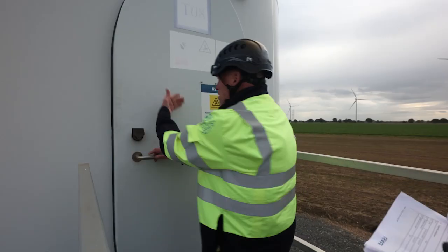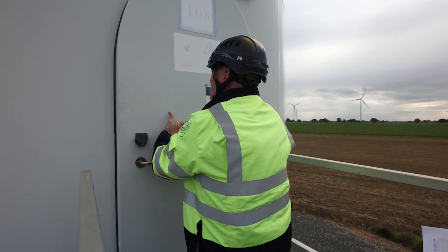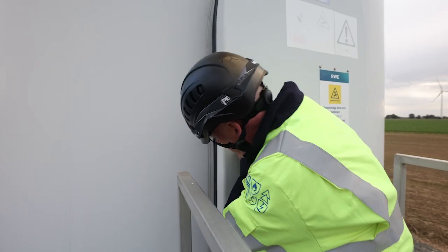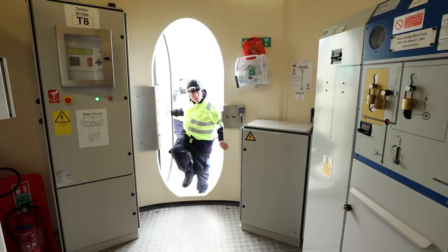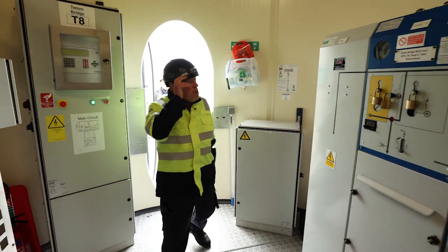We'd look for any evidence of a fire or overheating, things like smoke from the vents or the door handle being hot. And then what? We'd open the door slightly and check for any sounds and smells that could indicate that something's not right. Once we've confirmed all is good, then we would enter and look over the switchgear for any signs of distress or failure.